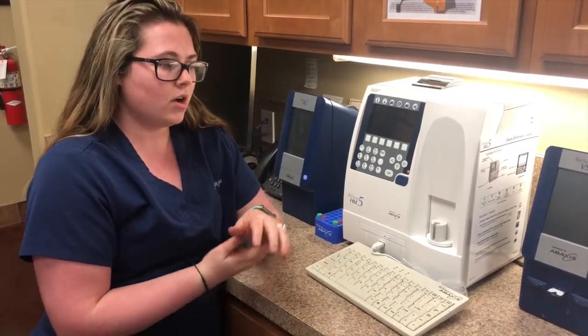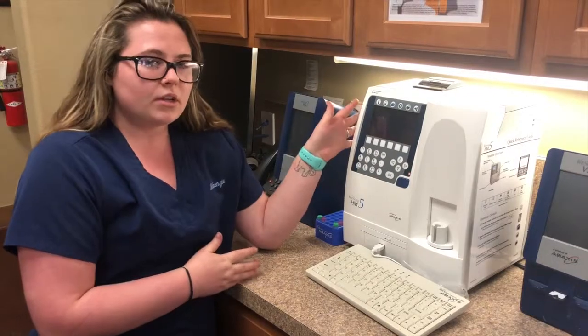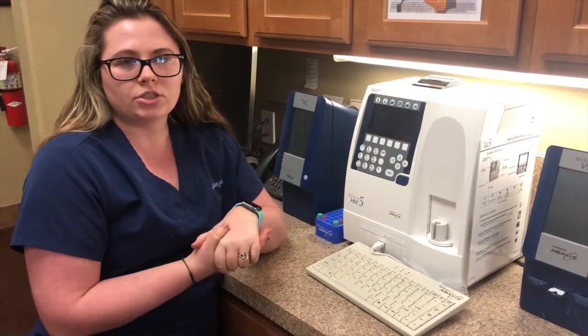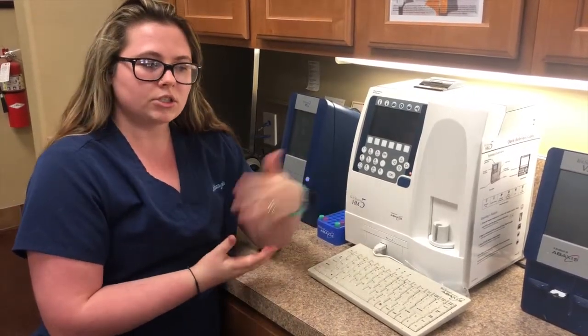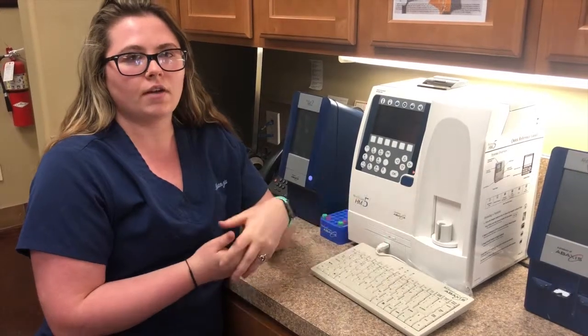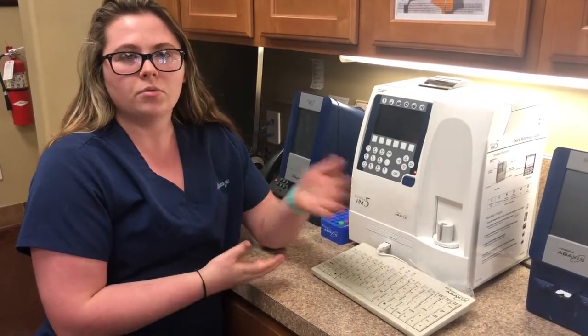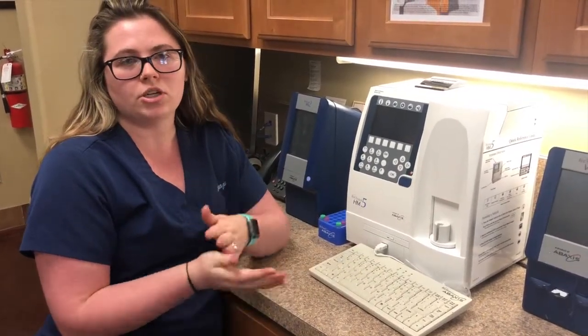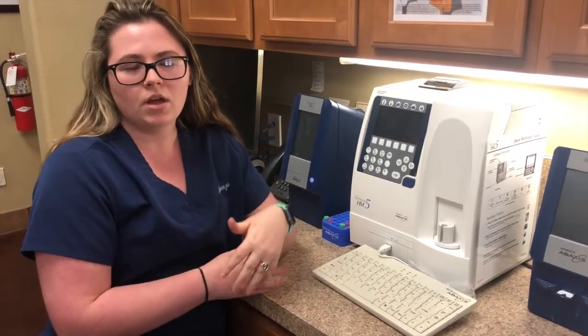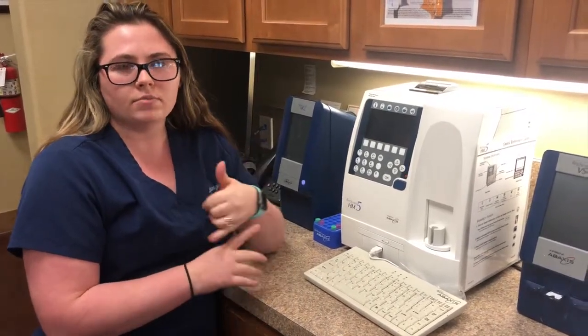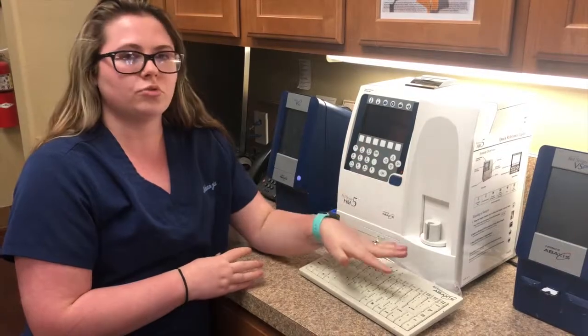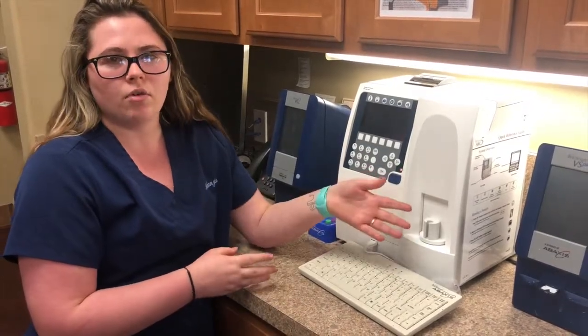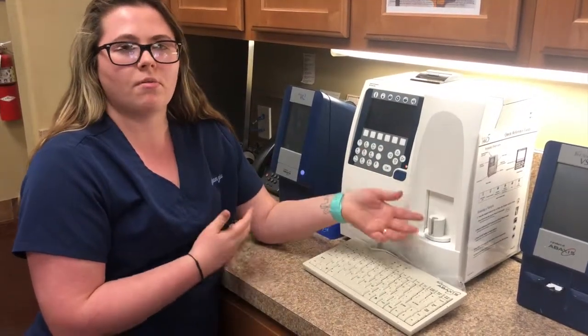And then there's also 6-month maintenance. So every 6 months we will have to change the reagent pack, or the more tests you run, just like the enzymatic cleaner, you may have to change your pack more often. When you do change your pack, you need to make sure you do change all the reagents and not just some of them. And then you also need to run a prime cycle to make sure all your quality controls are correct. And then you can also run a blood sample to make sure results come out as a test run.